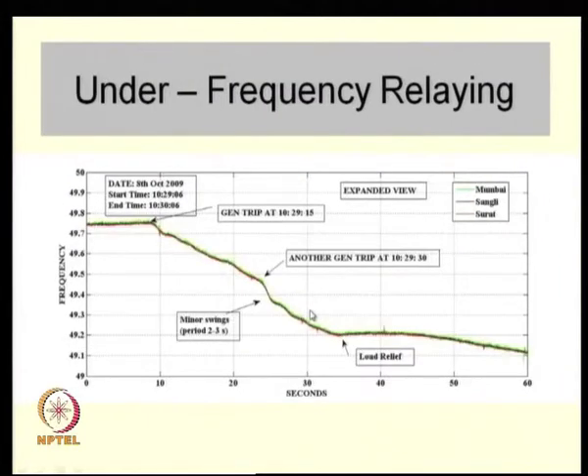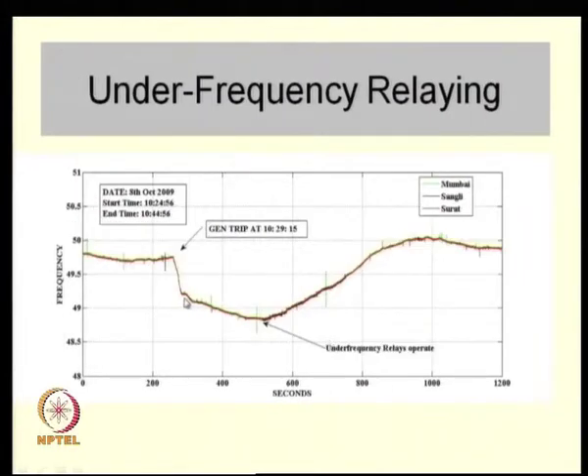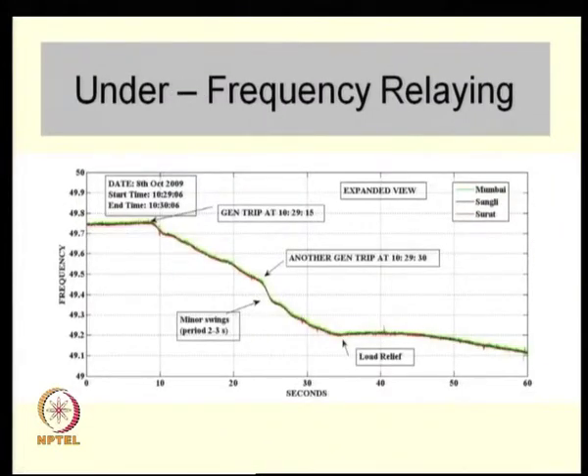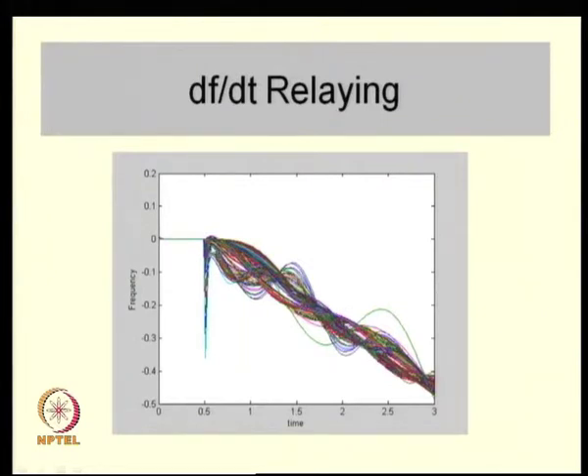Looking carefully at that event, there appear to be two generation trips and two load relief events. There are loads designed to trip when frequency falls, which is exactly what occurred, and after load tripping the frequency recovered. This is a kind of emergency control designed into the grid. A simulated response of a multi-machine system shows the rate-of-change-of-frequency at various buses after a generator trip, with the center-of-inertia frequency continuing to dip, showing the kind of information that can be used for quick control action.